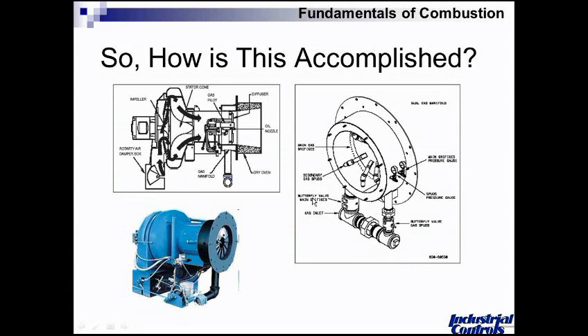On the right-hand side, we take our fuel from our gas train and our combustion equipment. Again, we think about this from the burner management system standpoint. There's going to be safety shutoff valves, gas pressure switches, all those types of safety devices that the fuel will pass through before it gets to the burner. On the right-hand slide, let's just assume those things are depicted, but the fuel comes in, goes through a butterfly control valve, and in this example, the fuel fills this firing head, which then passes through the main gas orifices. There's also a secondary valve on this particular model, which is used to control the flow of gas to the secondary gas spuds. There are two flame envelopes. One is somewhat pre-mixed, and the other one is more nozzle-mixed. It's done for strategic reasons and fuel air ratio and clean burning.